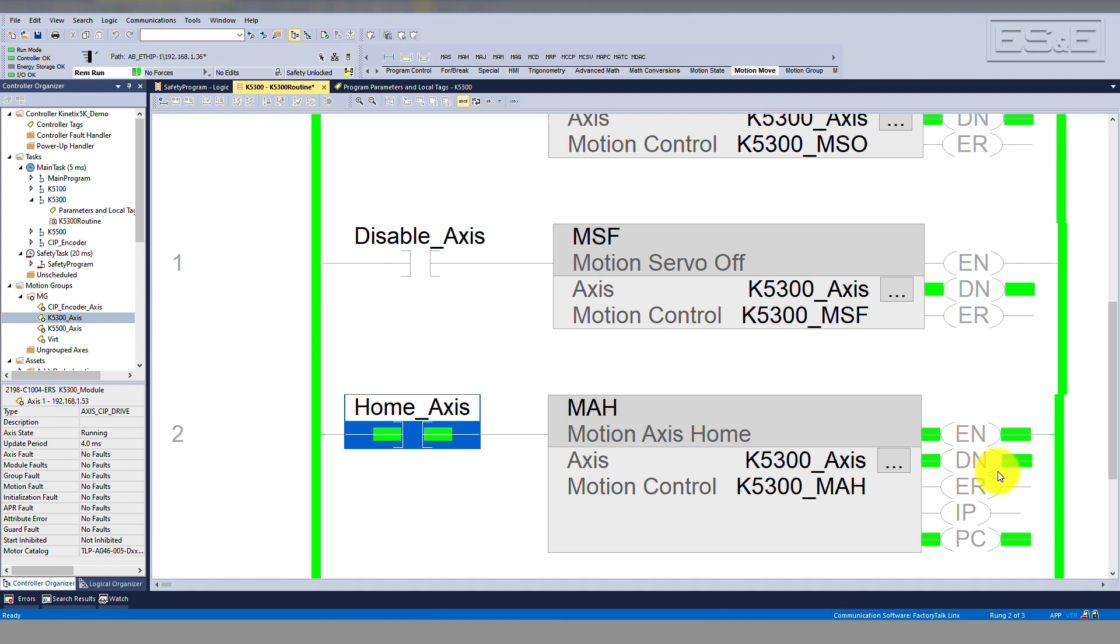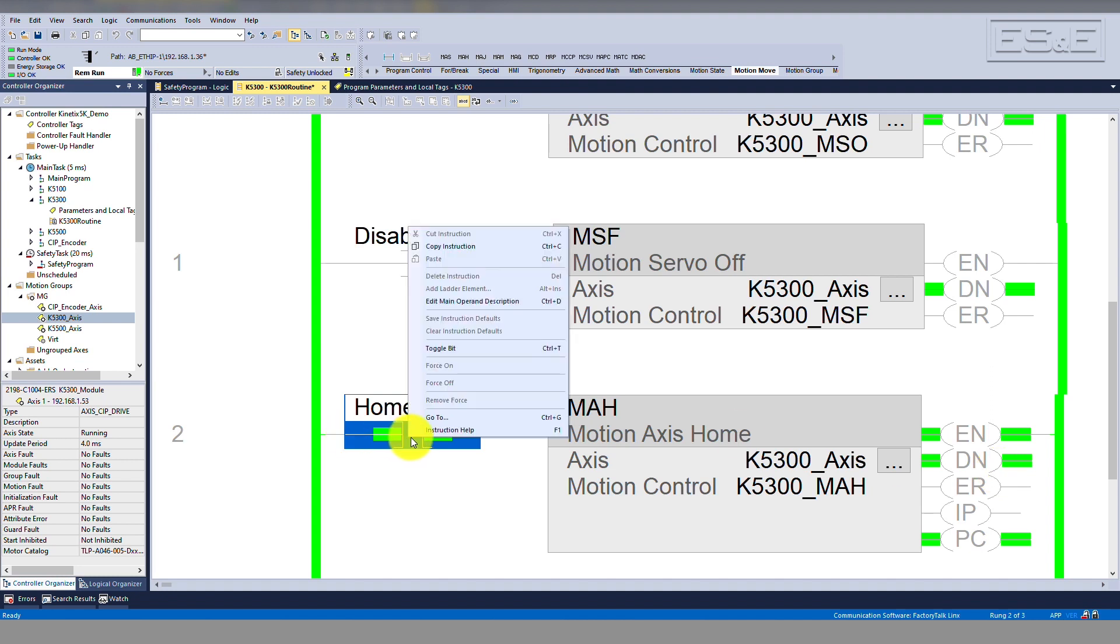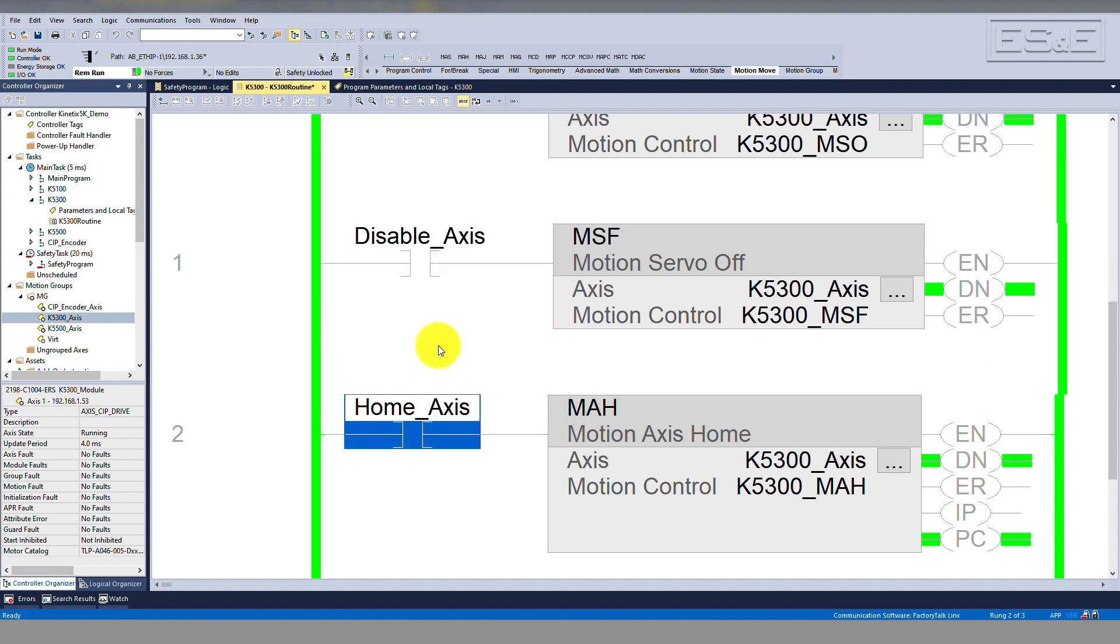As mentioned earlier, there are many different possible actions that the home instruction can take. We will discuss that shortly. When the rung transitions from true to false, you will see the enable bit transitions to false. This does not mean that the MAH instruction is no longer running. You will need to look at the IP and PC bits in order to determine if the home instruction has completed its task.